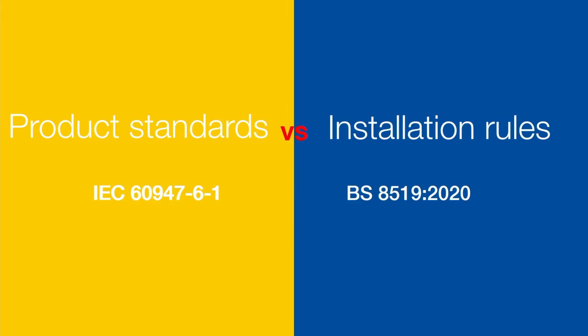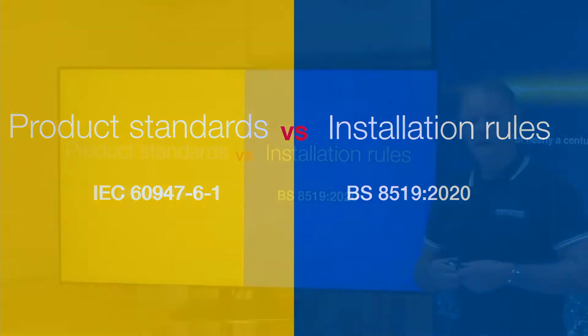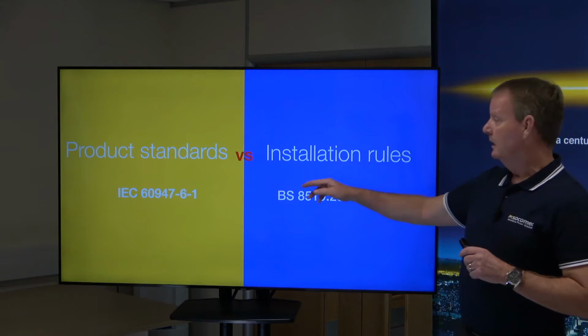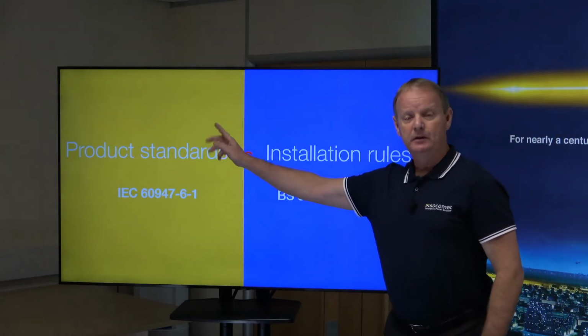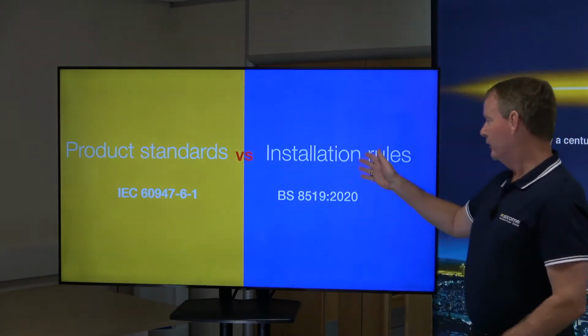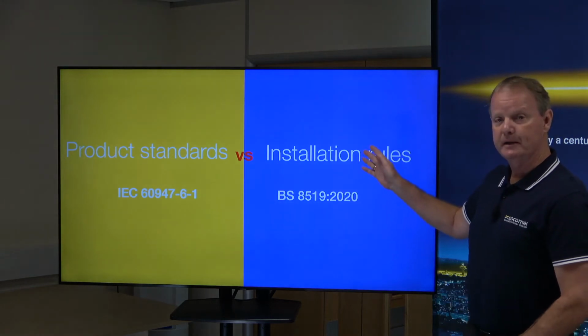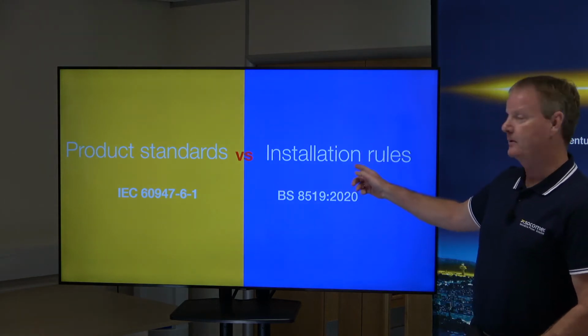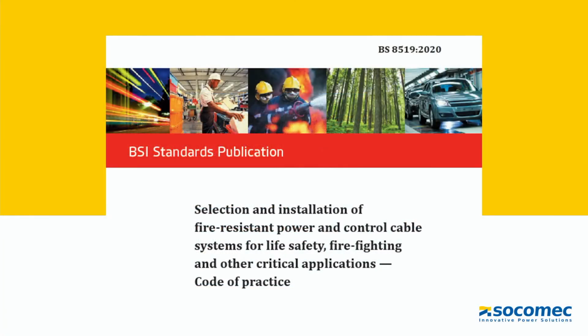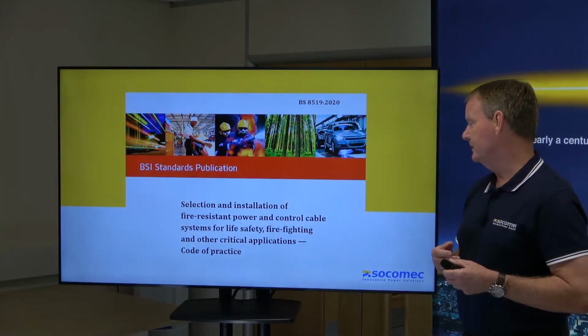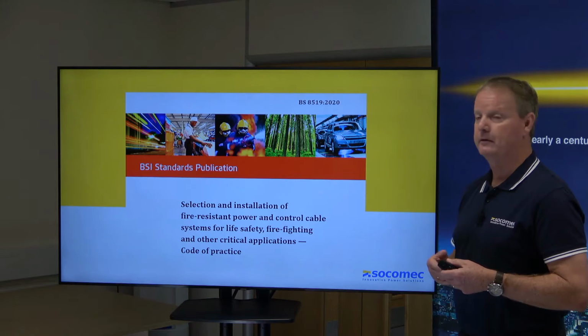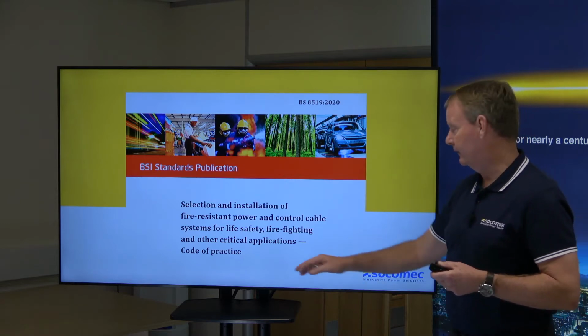So what are we going to talk about today? We're actually going to talk about an installation rule, so not really a product standard. The product standard hasn't changed, but the code of practice, or the installation rule, BS 8519-2020, has changed. Here you can see an image of the first page of the standard, and it's written around the selection and installation of power and control cable systems for life safety, firefighting and other critical applications. It's a code of practice, as it says at the bottom here.